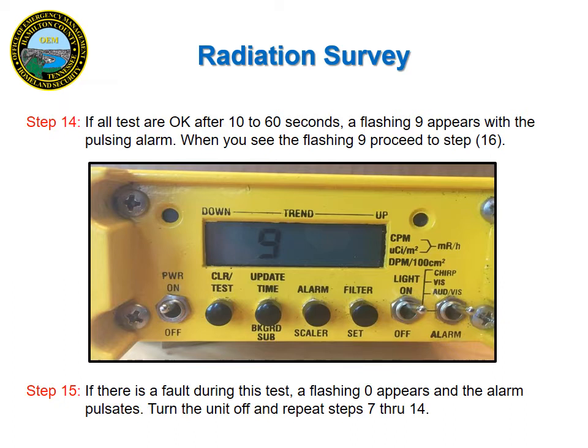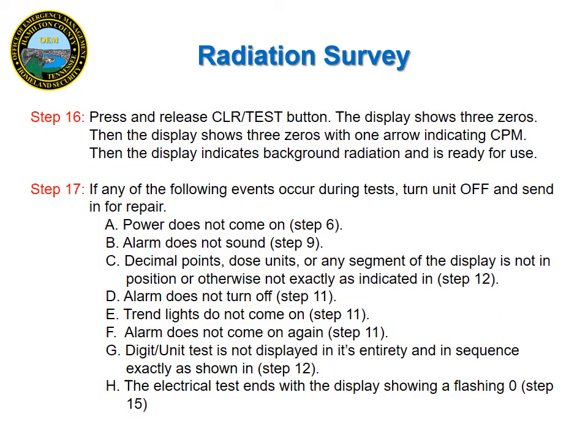But if something goes wrong and there's a flashing 0 that appears, turn the unit off and repeat steps 7 through 14. If everything is working, go ahead and press and release the CLR/test button. 3 zeros will appear with 1 arrow that will indicate CPM. At this point, you will also be receiving a background radiation count. When this happens, your meter is ready to use. If anything does not go correctly during the setup process, such as any of these issues listed on the screen, turn the unit off and send it back to the emergency management department for repair.